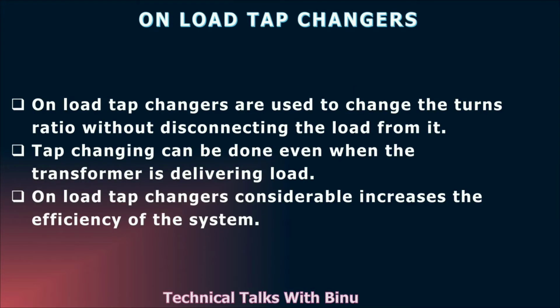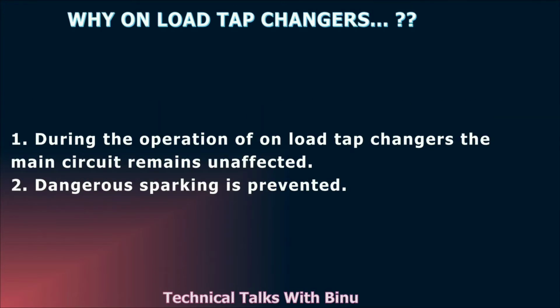Coming to on-load tap changer, these are designed to change the turns ratio without disconnecting the load from it. Which means that the tap changing can be done even when the transformer is delivering the load. So, OLTC is capable of increasing the efficiency of the system. Now, let's see the significance of an OLTC. As we have seen during the operation of an OLTC, the main circuit remains unaffected. Hence, the dangerous arcings are avoided.